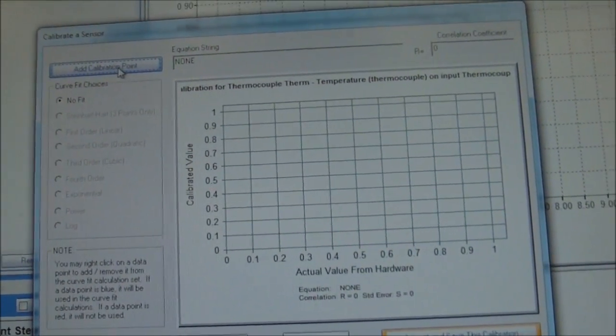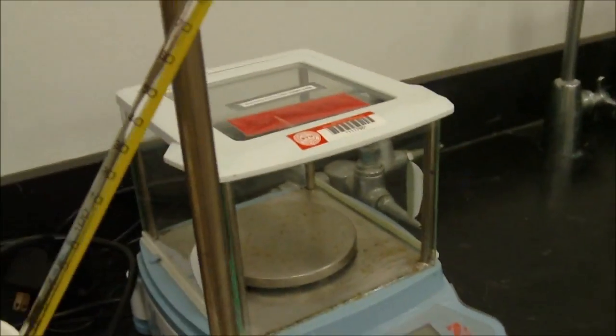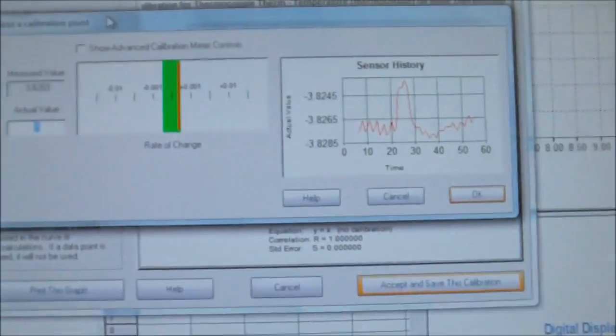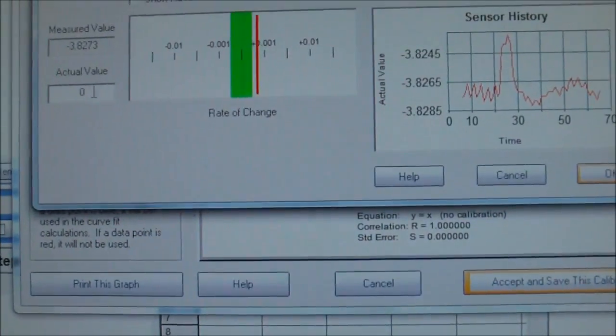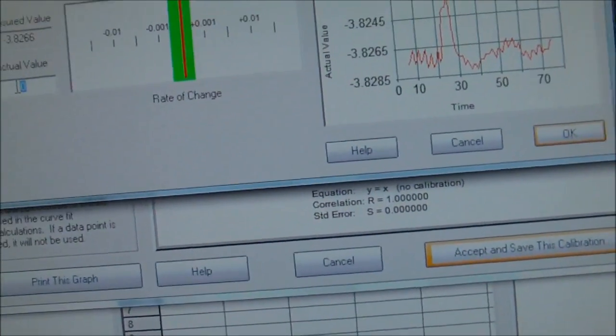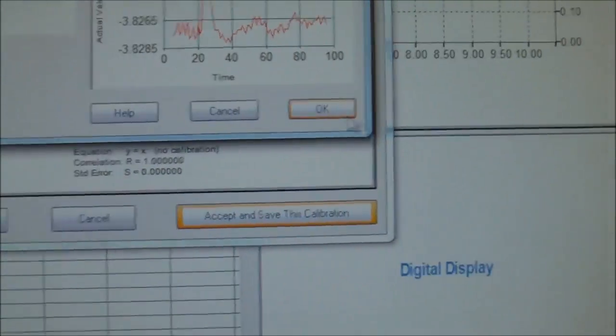We have to add a calibration point. The calibration point that we have in now is room temperature water. We can put our thermometer in there and check out the temperature of the water, right? We can monitor the temperature of the water. Type that value in here. And then we push OK.